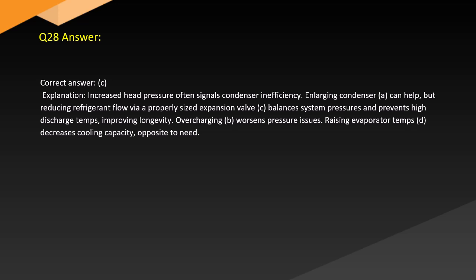Answer. Correct answer. C. Explanation. Increased head pressure often signals condenser inefficiency. Enlarging the condenser, A, can help, but reducing refrigerant flow via a properly sized expansion valve, C, balances system pressures and prevents high discharge temps, improving longevity. Overcharging, B, worsens pressure issues. Raising evaporator temps, D, decreases cooling capacity, opposite to need.